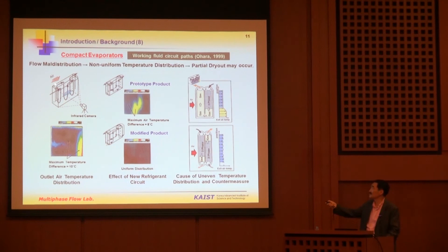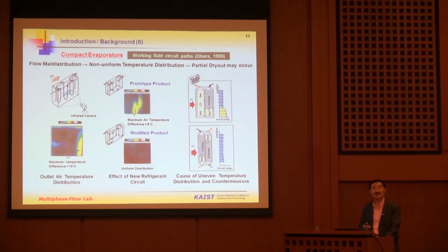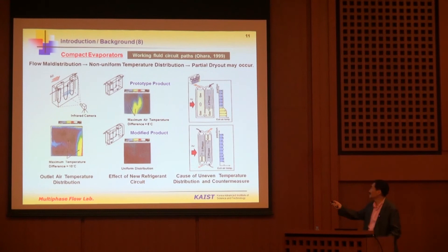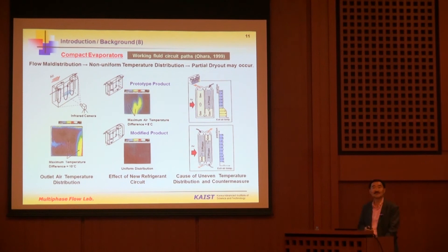The flow circuit determines the temperature distribution outside the heat exchanger. Some portions of the heat exchanger may not be cold enough, making the outside air temperature very different from place to place. To achieve uniform air temperature distribution, you need to find the proper refrigerant pass or circuit. The right circuit gives uniform distribution; the wrong one gives non-uniform distribution of air temperature outside the heat exchanger.